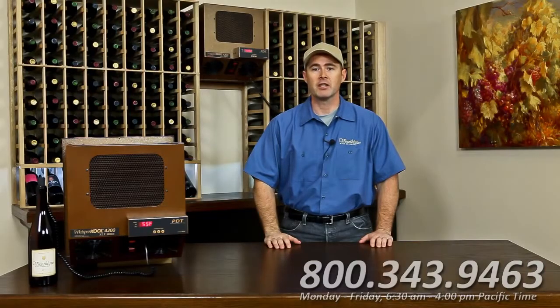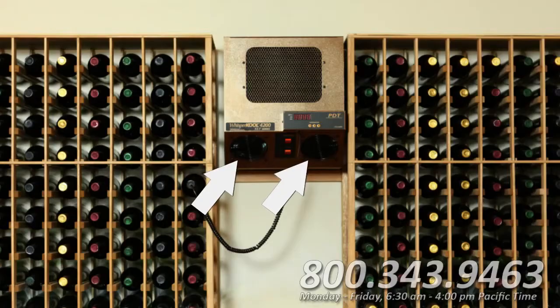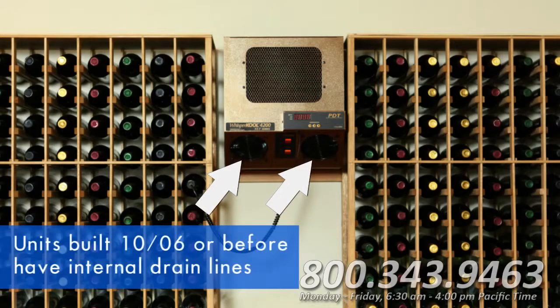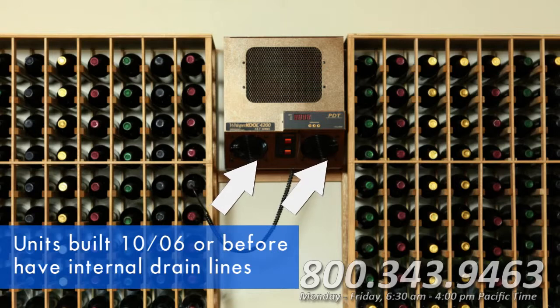Sometimes we get calls from customers who report that their cooling unit is leaking water. If your XLT was built in October 2006 or earlier and it is leaking from the front fans, the internal drain line might be clogged and you should call customer service for instructions. Models that are newer than October 2006 don't have an internal drain line.